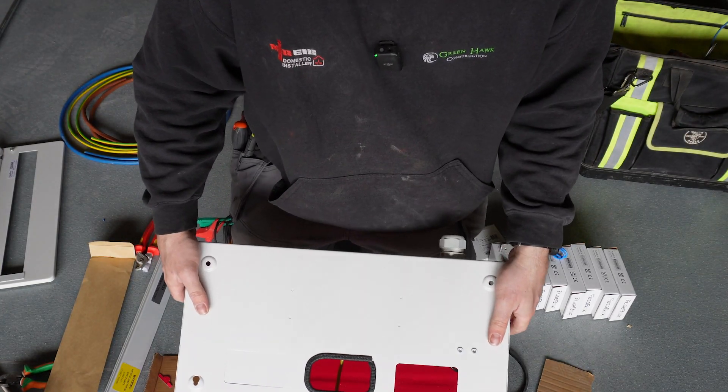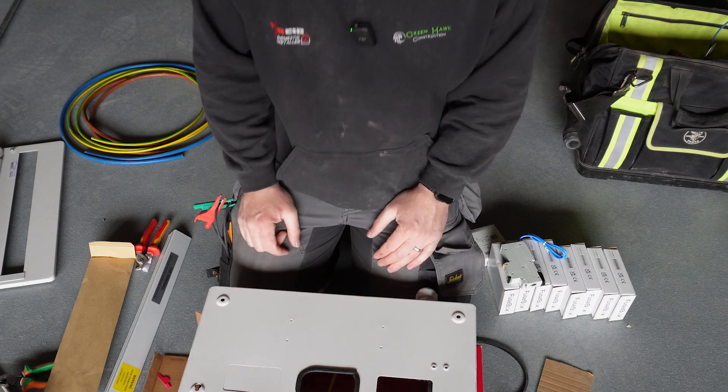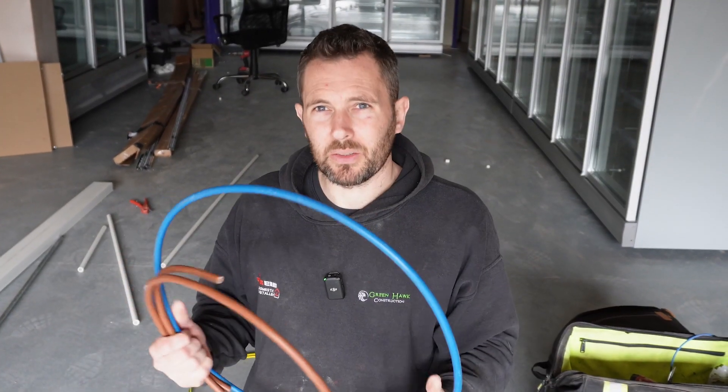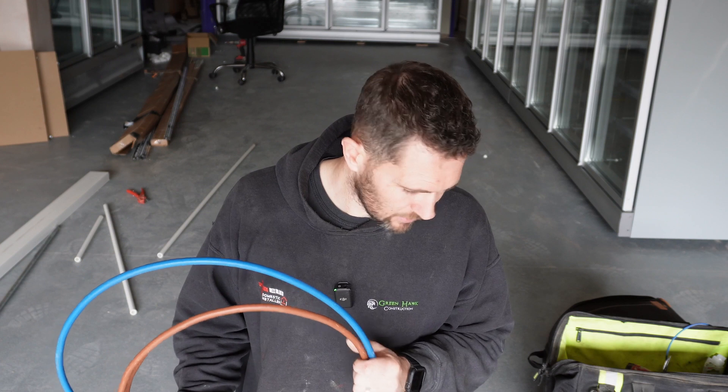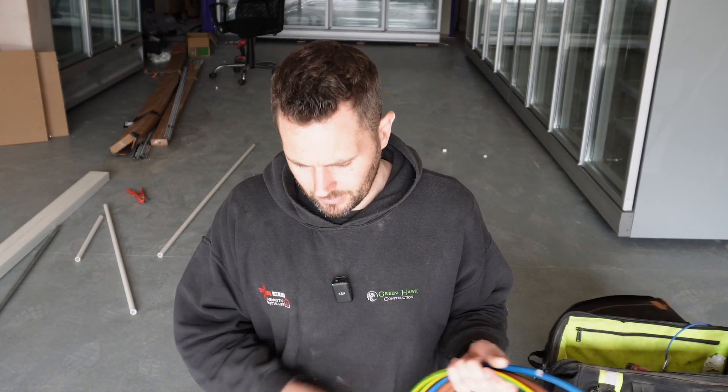That's one of them. Believe it or not, these are quite tricky to actually get on. Now we're onto the meter tails. We're using 25mm meter tails and 16mm earth as well.